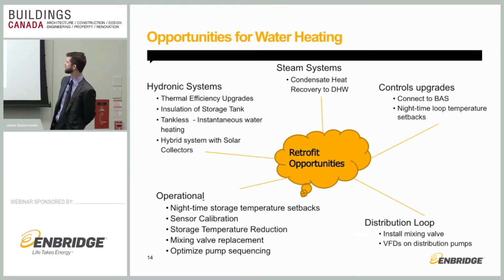On the distribution loop, you can install mixing valves, so you only supply a certain temperature of water to the tenant spaces. You don't need it to be blistering hot. Or VFDs on the distribution pumps can save a little bit as well. Operationally, we have similar types of things, nighttime setbacks, sensor calibration, all the same stuff I said before. So Enbridge helps with that as well.